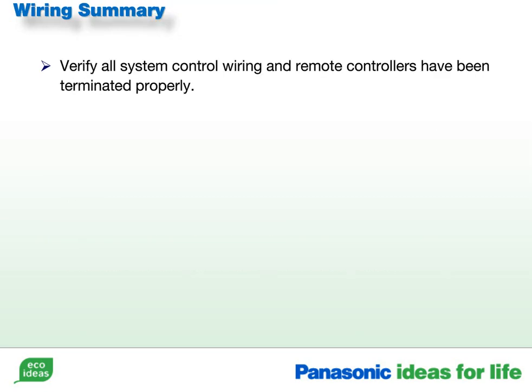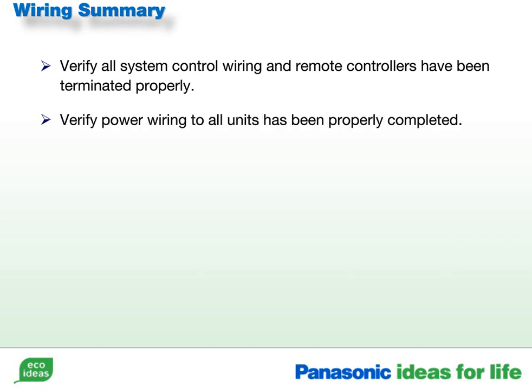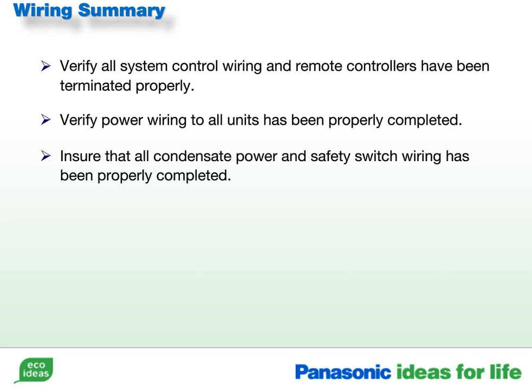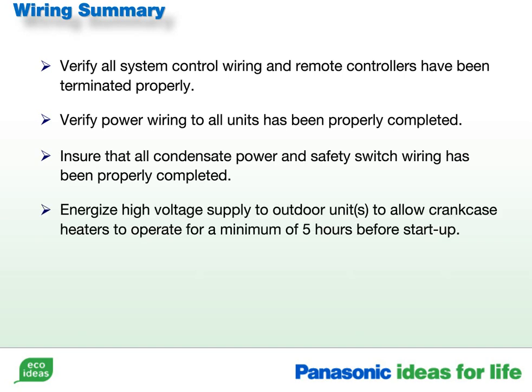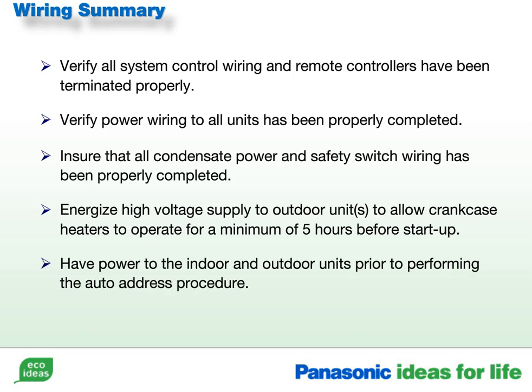Summary for the control wiring. Verify all control wiring and wired controllers have been terminated properly. Verify that the high voltage wiring to both indoor and outdoor units have been properly completed. Confirm that condensate power and safeties have been properly connected. Energize the high voltage supply to the outdoor units. Allow the crankcase heaters to operate for a minimum of 5 hours before the condenser's first run. Make sure all of the air handlers and condensers have had the power applied before initiating the auto-address procedure.